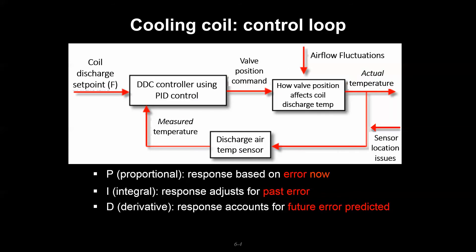There's a bit much to swallow, but we looked at applications like a cooling coil and how we're trying to tell a valve what position to be in so we can generate enough chilled water flow through that cooling coil to get the discharge air temperature that we want. We've got some things against us like sensor location issues, noise associated with inaccuracy, disturbances in our system, and different feedback lags. But this is the idea - this is how a closed-loop control process works.